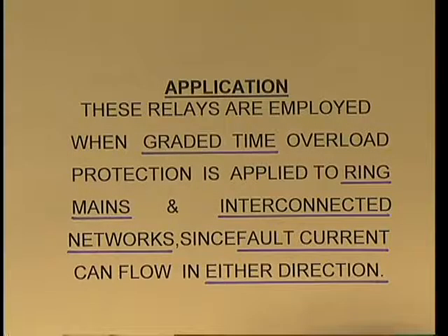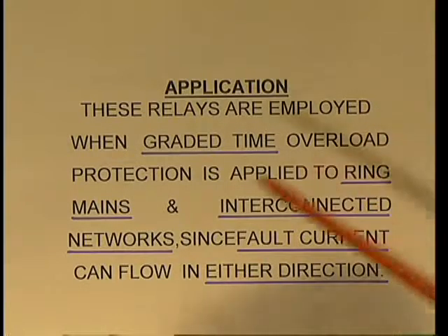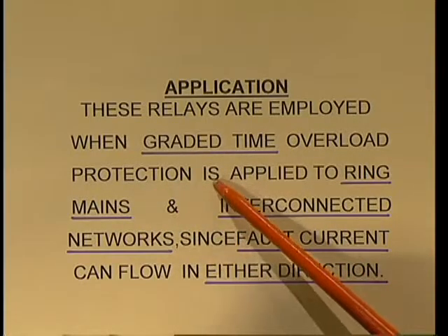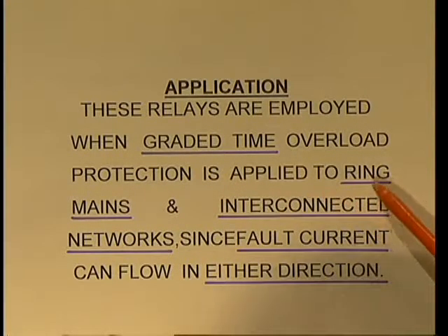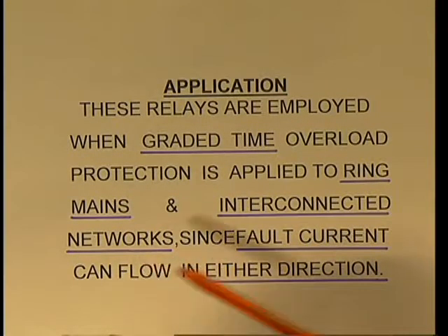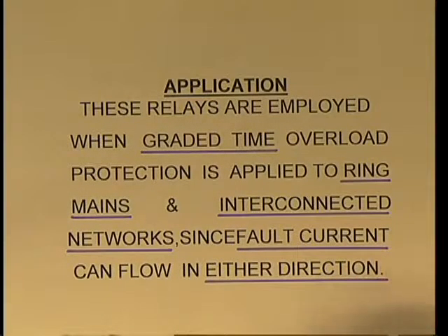The applications of directional overcurrent relays are these. These relays are employed when graded time overload protection is applied to ring mains and interconnected networks, since fault current can flow in either direction. So there these relays are used. These are the applications of the directional overcurrent relays.